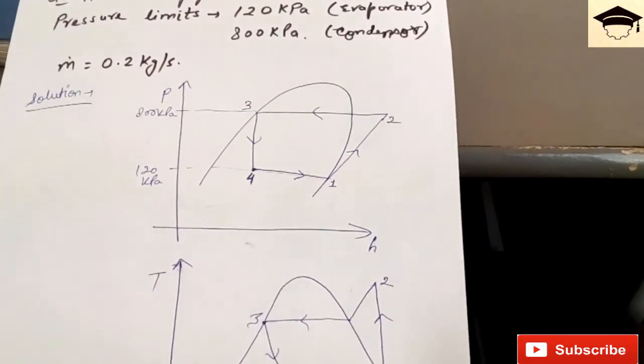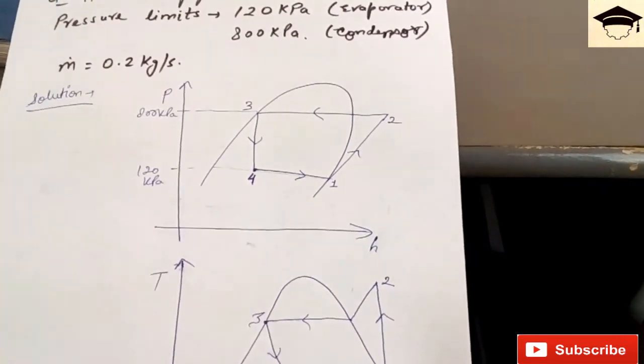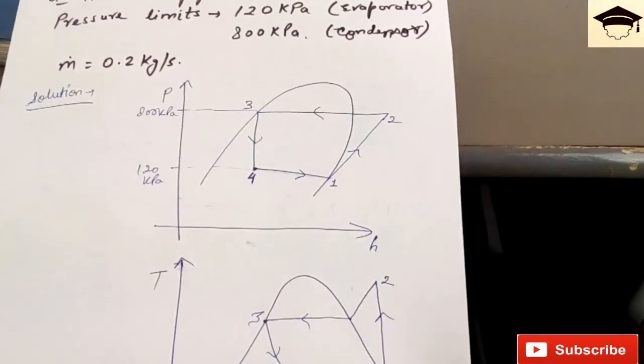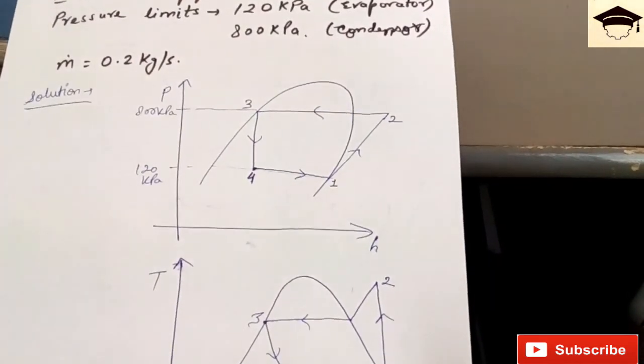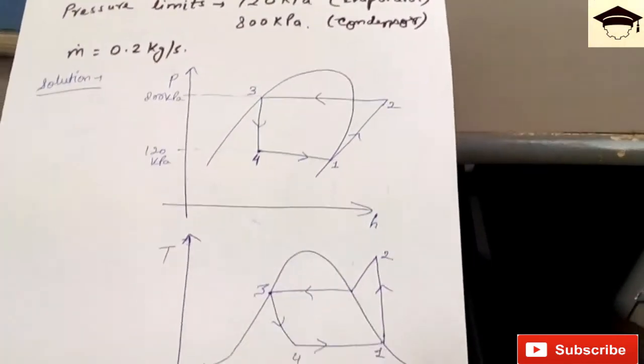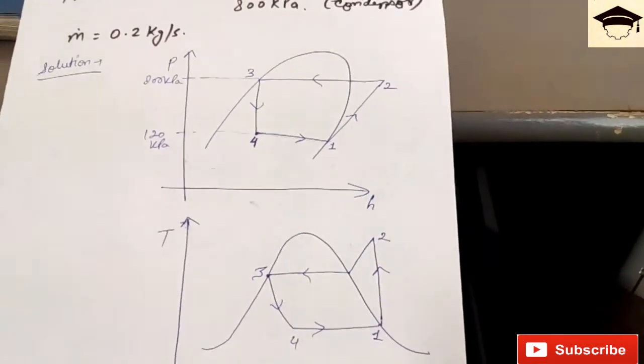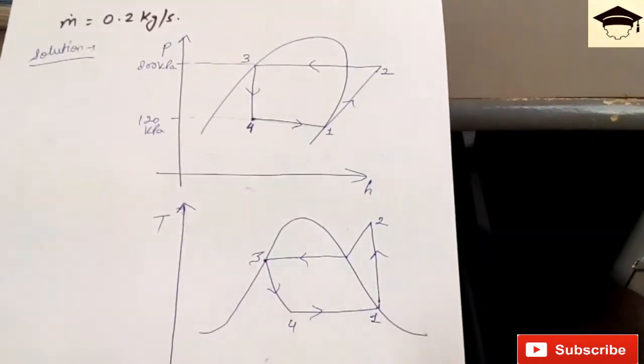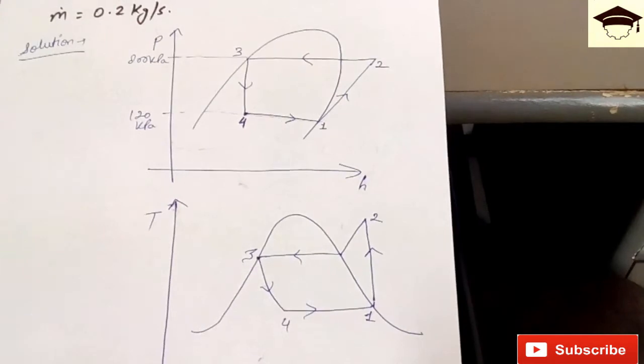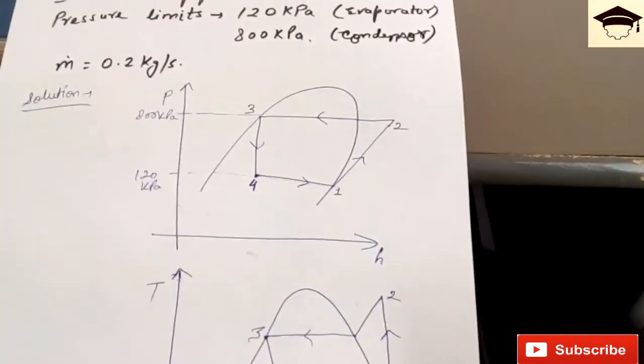Now from the pH chart I have taken the values corresponding to these pressures. h1 is equal to 237 kilojoules per kg, and h3 is equal to h4 is equal to 95.5 kilojoules per kg. h2 is equal to 276.45 kilojoules per kg.